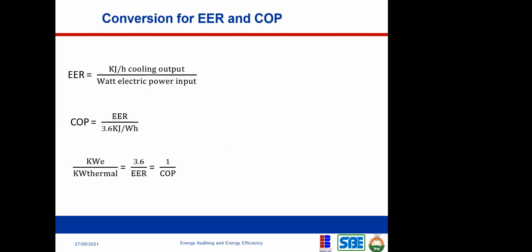So now we can convert EER to COP. Assuming that you have a heat pump and you're given the COP, but somebody is asking, look, I want this value in EER. I want to know what the COP is, I want to know what it is in EER. Okay, how do you do that conversion? That is where this conversion formula comes into play, right? Kilowatt electrical, that's electrical energy input, divided by the kilowatt thermal, is equal to 3.6 over EER, which is also equal to 1 over COP.